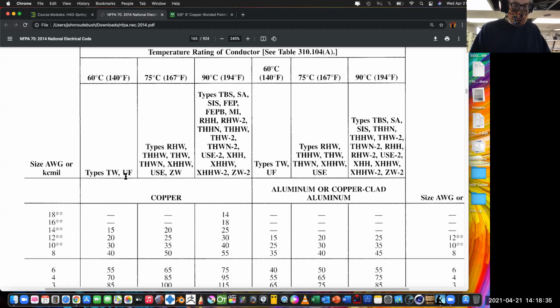If it is TWUF... well, I can tell you the insulation that I always use, if I can, is THWN-2, which we've talked about in a previous class. That means it is thermoplastic and high temp. In other words, it's a combination of THHW, so it is able to be used in wet locations or submerged water, not just damp. But because it has this 2, it is also rated for a high temperature.